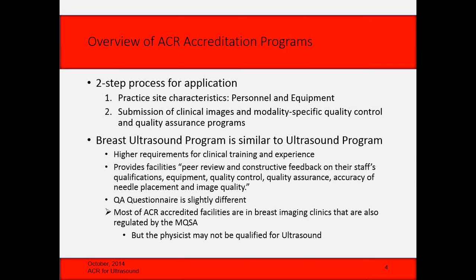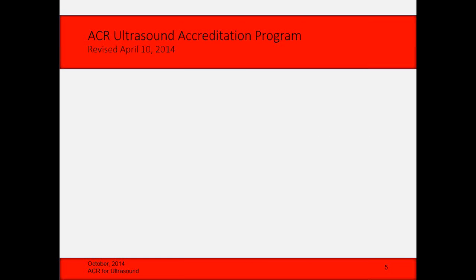Part of that is that they're required to have a physicist either on staff or as a consultant. But quite often in my experience, that physicist may not be qualified for ultrasound. Unless they've studied some of the ultrasound physics and the unique part of that, they may not actually be qualified to do this job. Fortunately, the ACR has accommodated for that. That's one of the main changes they made for 2014.